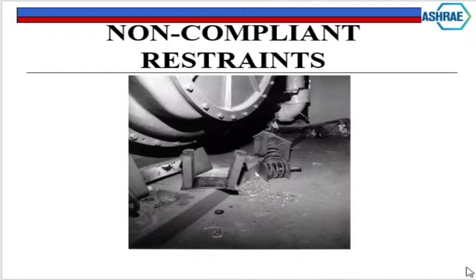These were, as you can see, what we call high deflection. This was probably a 75 to 100 millimeter deflection spring, which are physically big, okay? Now what they have is this little thin 6 millimeter plate, which as you can see, bent all over the place. They got big, beautiful, strong, beefy channels, but they're connected to this little 6 millimeter plate. They got one hole on that side for anchorage and one hole on the other side for anchorage. Basically no anchorage because the plate isn't wide enough, and they put one anchor in the very center. So it just teeter-totters off that until the point where it breaks off and everything goes, right?